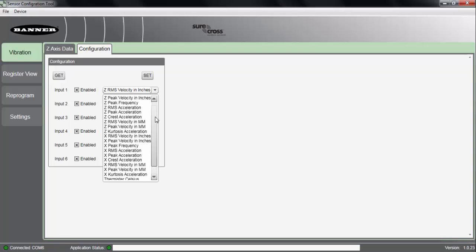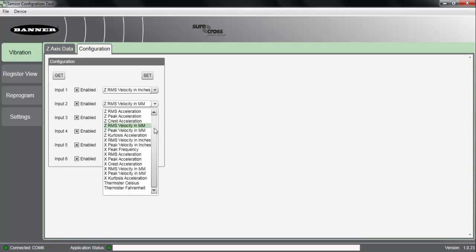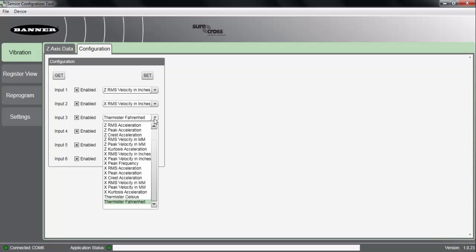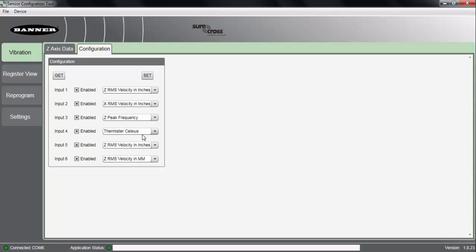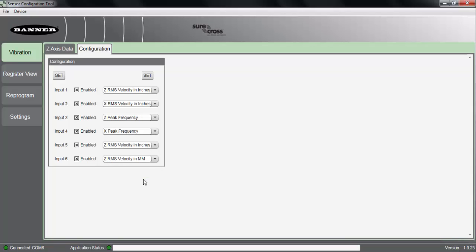And as you can see, we can change our registers. So, for instance, if we wanted to see the z-axis velocity, but we also wanted to see the x-axis velocity, and maybe instead of temperature, maybe we're more concerned with the frequency of that vibration for both the z and the x-axis.